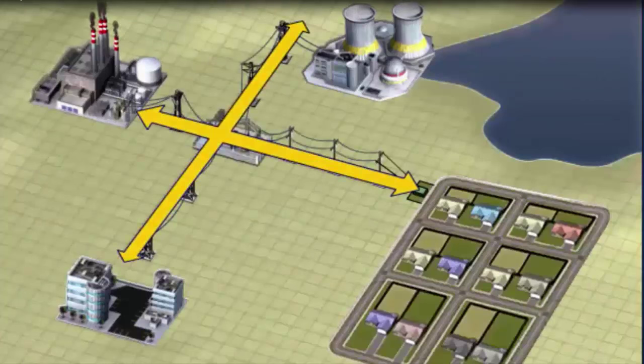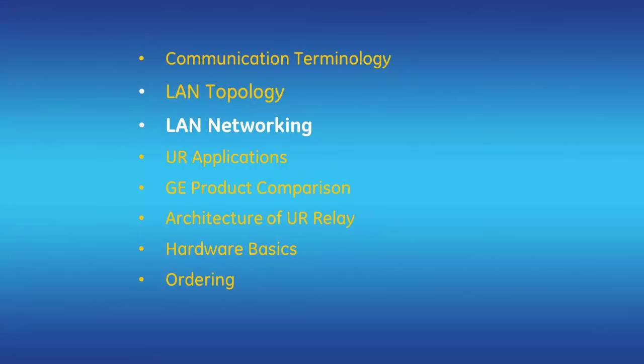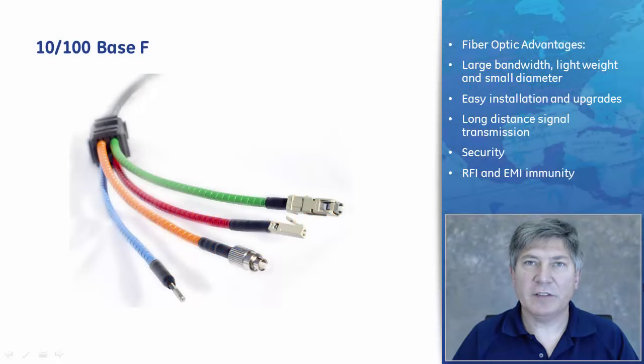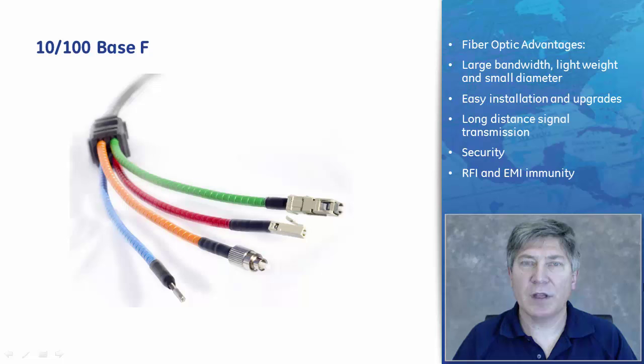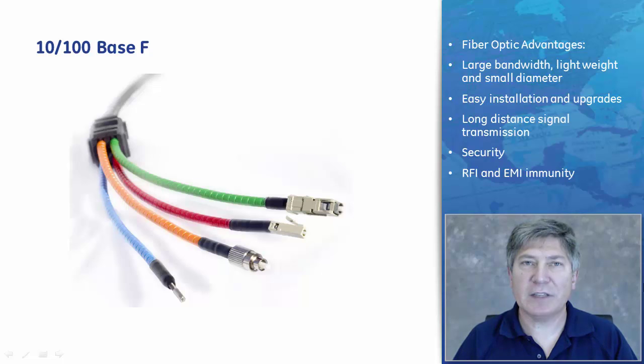In power system applications where communications over larger distances are required, fiber-optic Ethernet is preferred. Fiber has an advantage over 10/100 Base-T in that it is immune to EMI (electromagnetic interference) and RFI (radio frequency interference). A basic fiber-optic system consists of a transmitting device to generate the light signal, an optical fiber cable to carry the light, and a receiver to accept the light signal. Fiber-optic systems offer advantages including large bandwidth, light weight and small diameter, easy installation and upgrades, long-distance signal transmission, security, and non-conductivity.